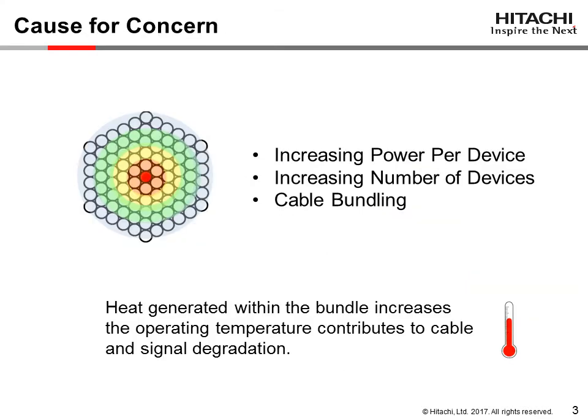Increasing the power per device, and increasing the number of devices, coupled with the industry standard practice of cable bundling, is a cause of concern. All this power generates heat within the bundle, and may increase the temperature of the cables above their maximum operating temperature, contributing to actual cable degradation.